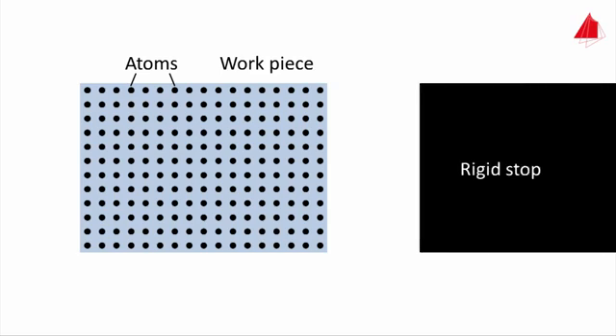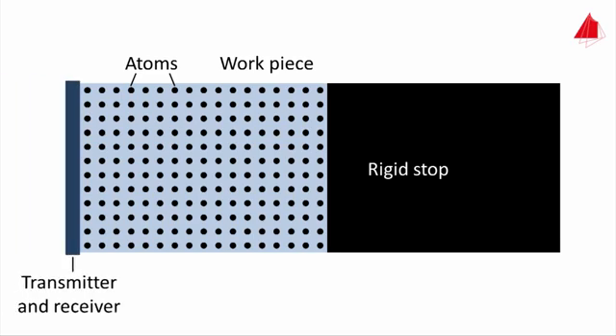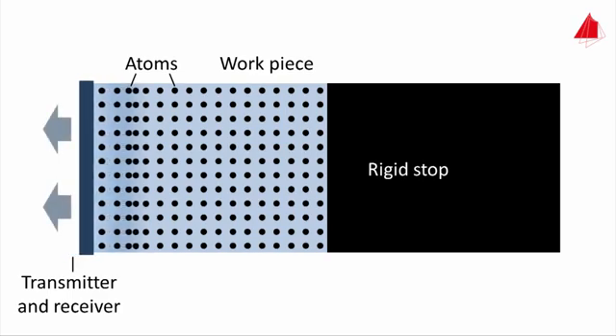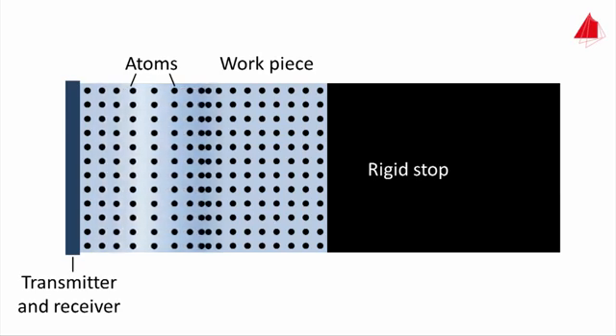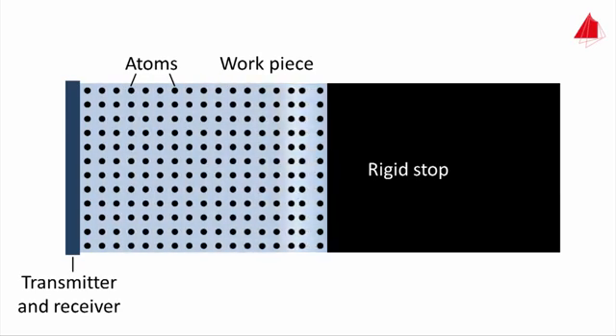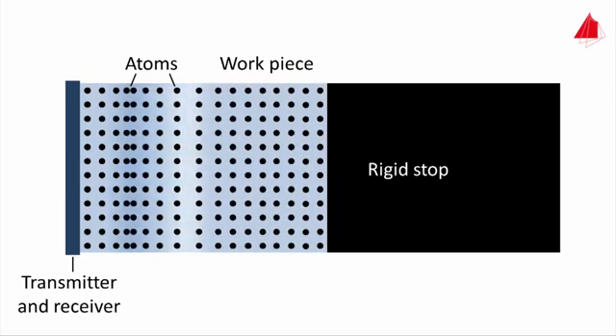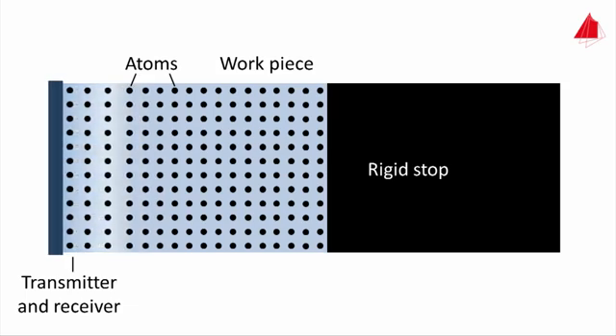To begin with, a rigid unyielding stop is attached to the right front end of the cylinder. At the left front end, a disc is installed to transmit and receive sound waves. Pushing and pulling briefly at the disc causes a longitudinal sound wave to propagate through the cylinder. When the sound wave reaches the rigid stop at the right side, it is reflected and runs back towards the disc, which now serves as a receiver.